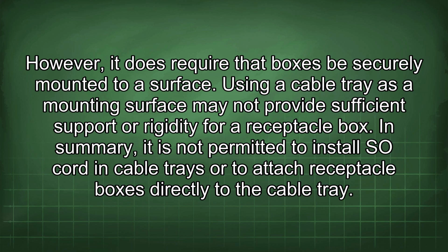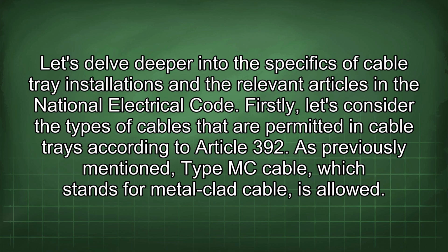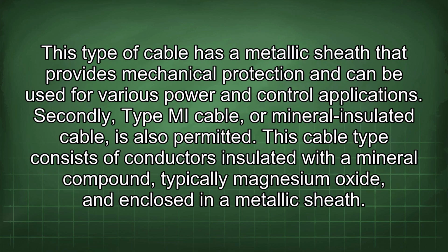cable tray. Let's delve deeper into the specifics of cable tray installations and the relevant articles in the National Electrical Code. Firstly, let's consider the types of cables that are permitted in cable trays according to Article 392. As previously mentioned, Type MC cable, which stands for metal-clad cable, is allowed. This type of cable has a metallic sheath that provides mechanical protection and can be used for various power and control applications. Secondly, Type MI cable, or mineral insulated cable, is also permitted.